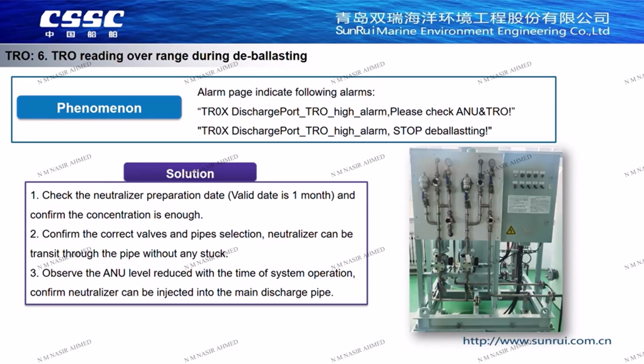If the reagent and the solution are in normal condition but TRO is still high in deballast operation, then check the neutralization line. Make sure the neutralizer injects into the correct pipeline. Observe whether the liquid level of the neutralization tank drops normally when the metering pump is running, and check whether the neutralizer has been pumped out. Generally, increasing the concentration of neutralizer can solve the problem of a high concentration of discharged TRO.